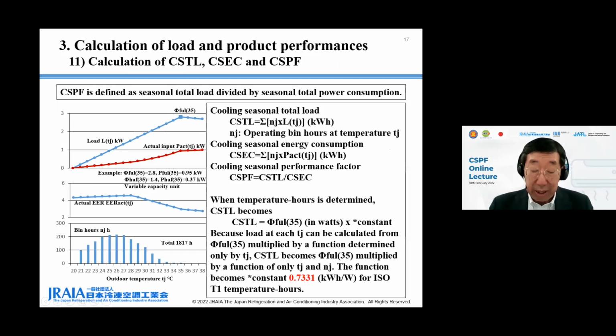Okay, this page shows calculation of CSTL, CSEC, and CSPF. Cooling seasonal total load CSTL is the sum of load at each outdoor temperature TJ multiplied by bin hours NJ. Cooling seasonal energy consumption CSEC is the sum of actual input at each TJ multiplied by bin hours NJ. Cooling seasonal performance factor CSPF is total load CSTL divided by total energy consumption CSEC. CSPF is a kind of weighted average of actual EER for all operating temperatures from 21 to 35 degrees C.